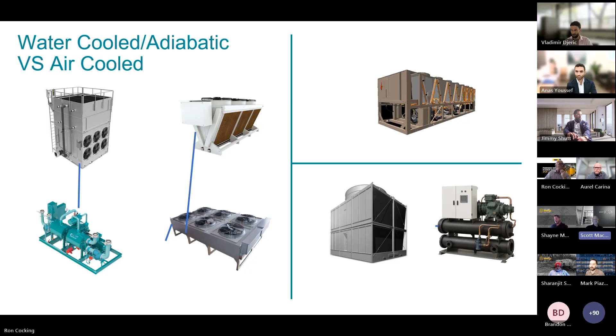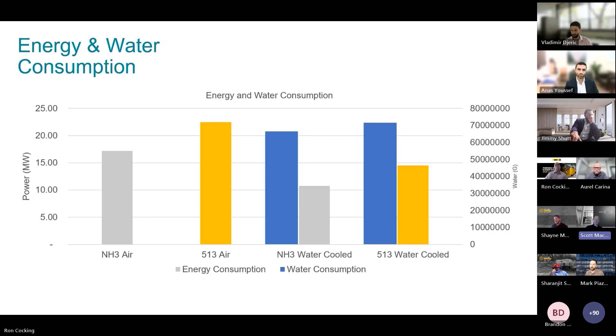What we're calling out on this slide is a comparison of two packages: an R513 on the far right, and beside it an ammonia package of the same capacity. On the far right, you can see power consumption in yellow and water consumption in blue. Both energy and water consumption in the ammonia package are greatly reduced in those circumstances. If we need to go fully waterless, one thing to note is that while both the R513 solution and the NH3 solution can achieve this, the energy penalty to go with ammonia is only one third of the penalty we pay when we go waterless with R513. Next slide.